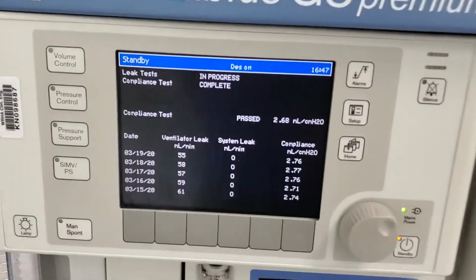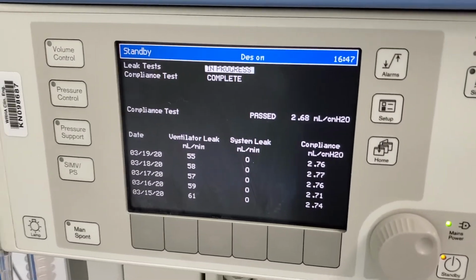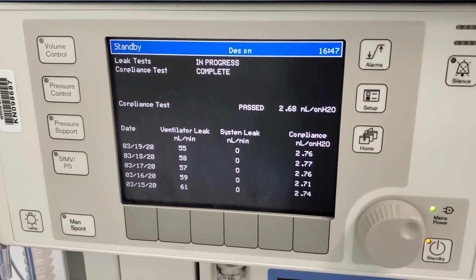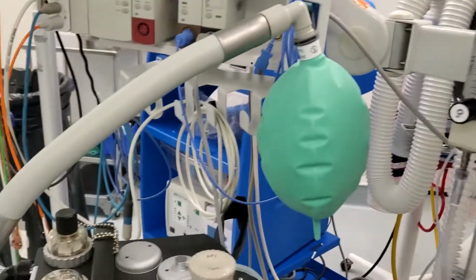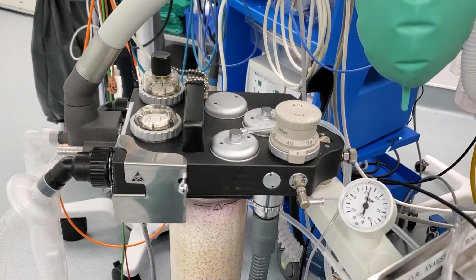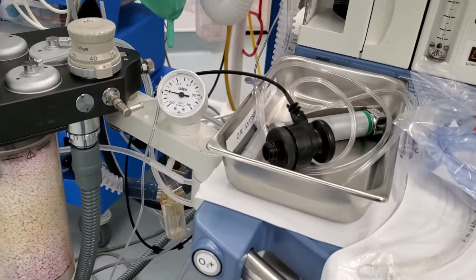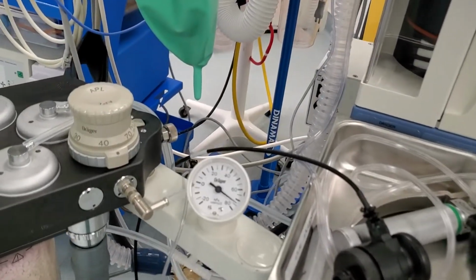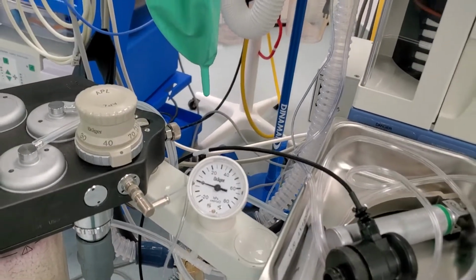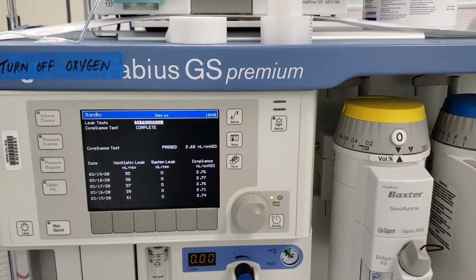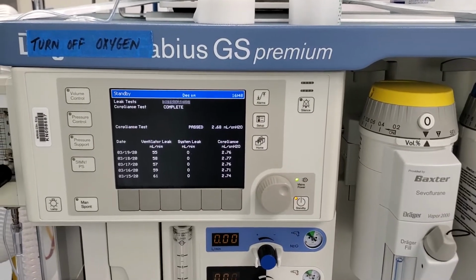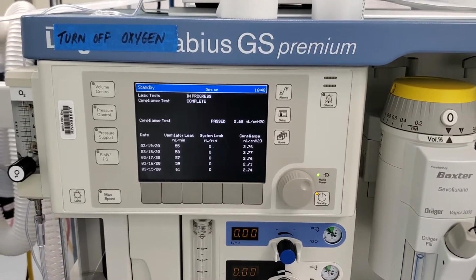But in adults, we only do this test once in the morning, not every time a new circuit is put on. We do a manual leak test, which just involves closing the APL valve and pushing the O2 flush button, watching the pressure gauge to build up a pressure to ensure that there are no leaks in the system. And I'll show you that as soon as this total leak test is finished.